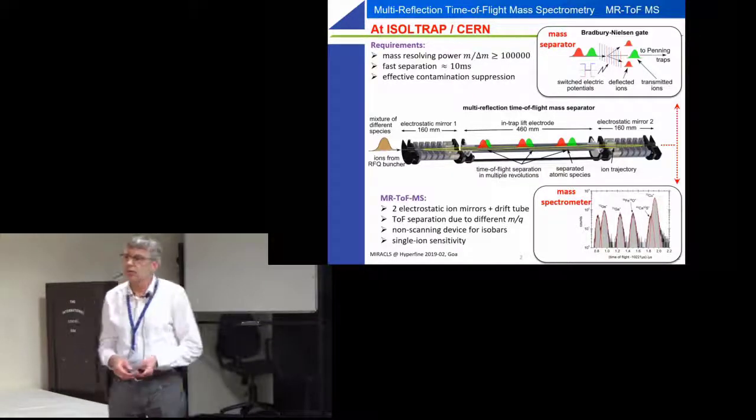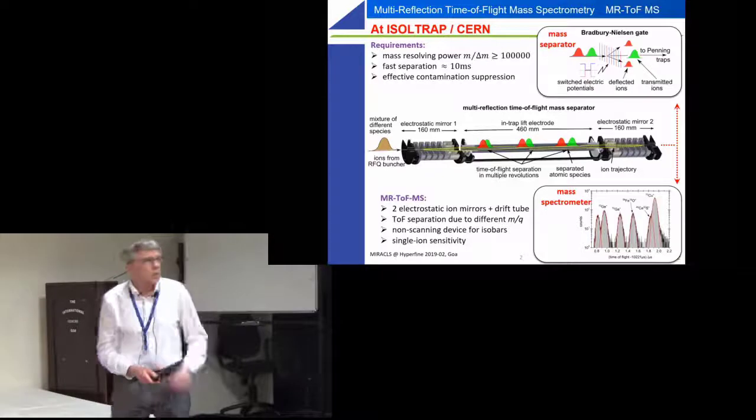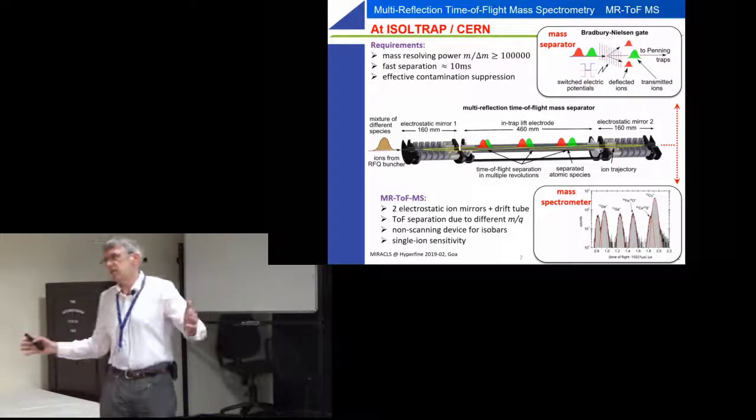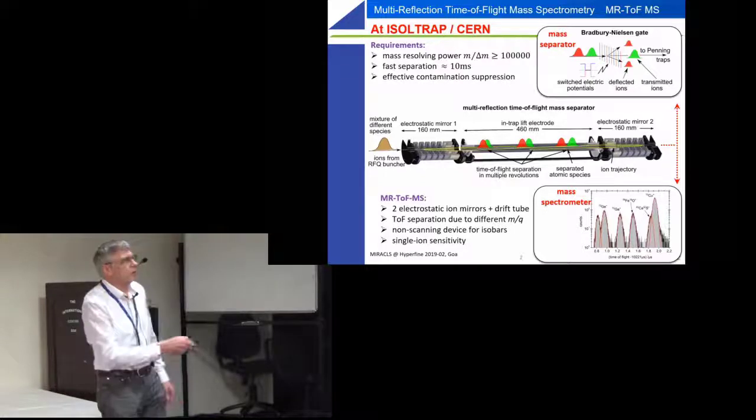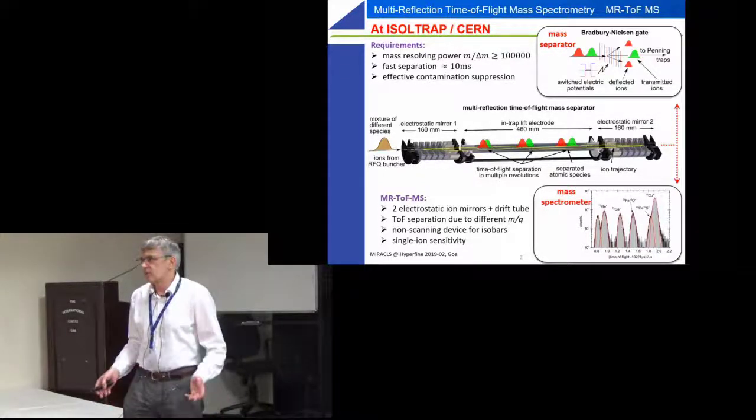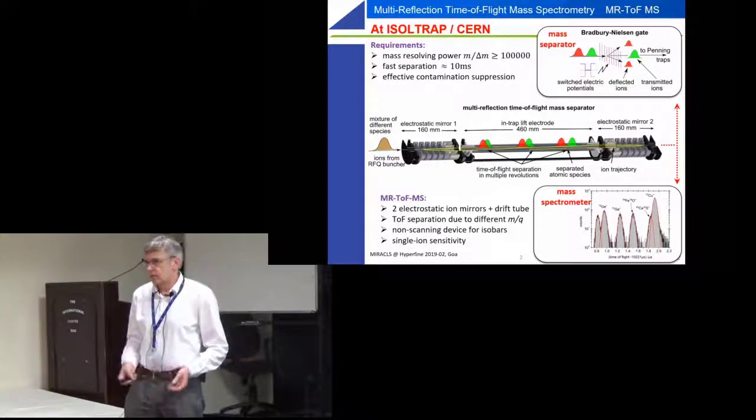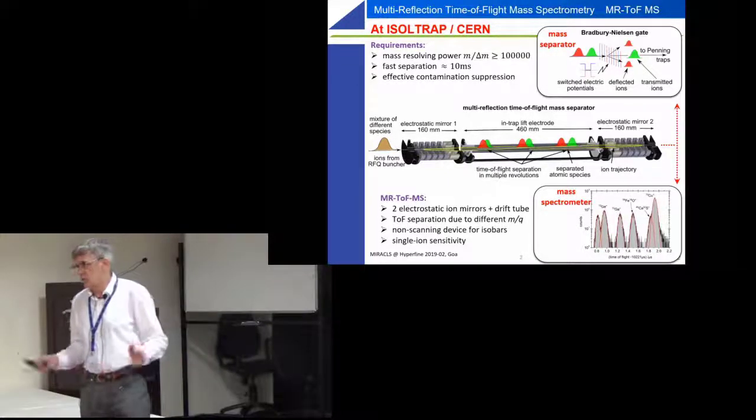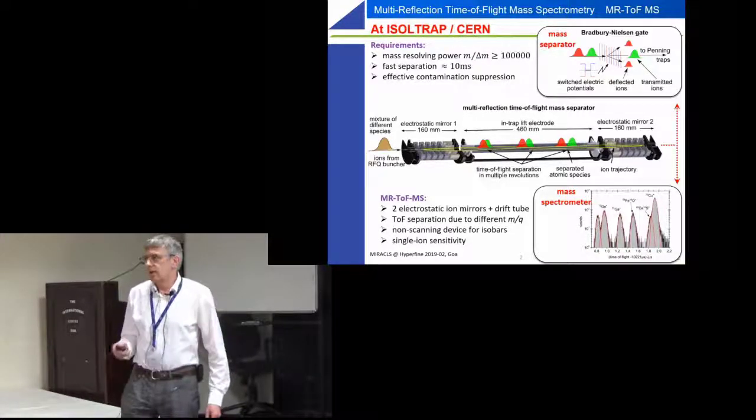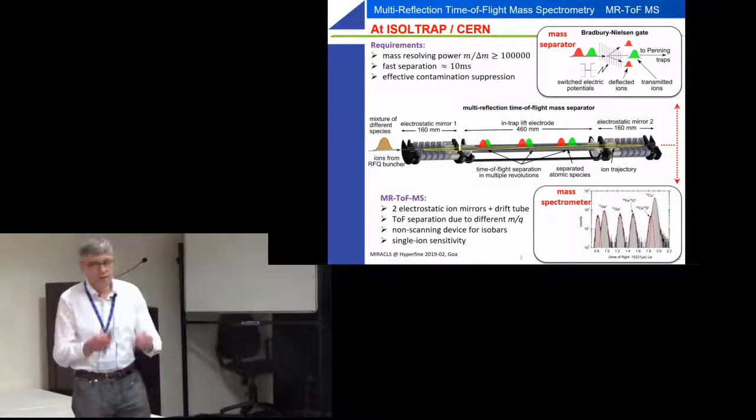Instead of building an instrument kilometer long, we inject the ions into a meter size instrument and let them go back and forth a thousand times. That's where you get very high resolution - resolving power 100,000, 200,000, 300,000 and the corresponding precision in the mass value.